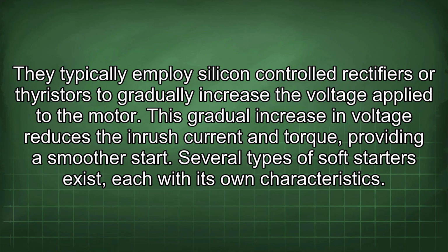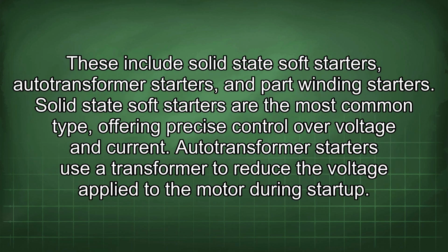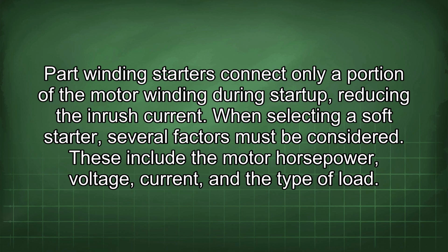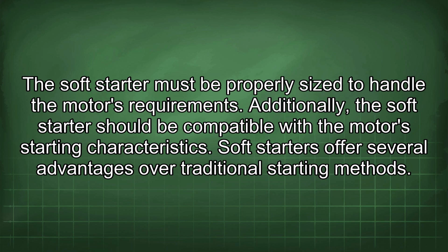Several types of soft starters exist, each with its own characteristics. These include solid-state soft starters, auto-transformer starters, and part-winding starters. Solid-state soft starters are the most common type, offering precise control over voltage and current. Auto-transformer starters use a transformer to reduce the voltage applied to the motor during startup. Part-winding starters connect only a portion of the motor winding during startup, reducing the inrush current. When selecting a soft starter, several factors must be considered. These include the motor horsepower, voltage, current, and the type of load. The soft starter must be properly sized to handle the motor's requirements. Additionally, the soft starter should be compatible with the motor's starting characteristics.